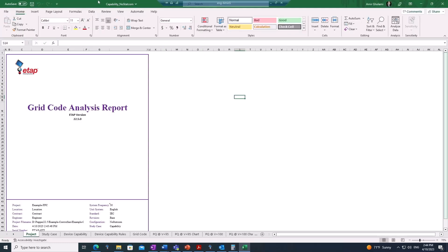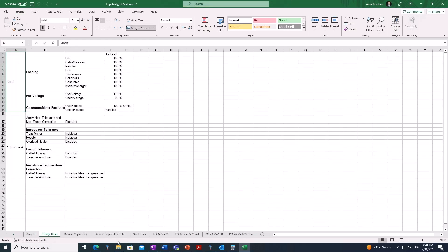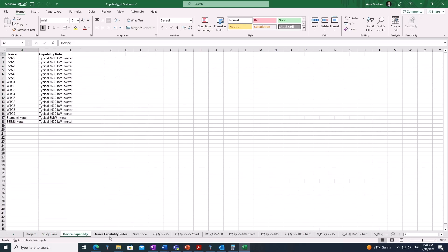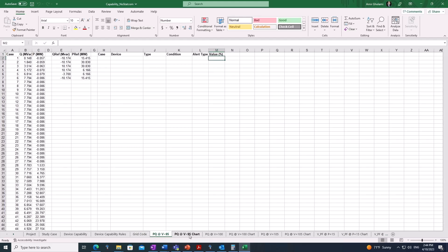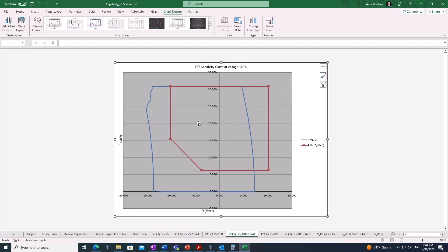Running the 'capability no STATCOM' scenario generates a report as soon as the studies are completed. The report includes various sheets covering multiple pieces of information regarding device capabilities, the grid code being used, and calculation results at different voltage levels — at 95% and 100%. The results are also visualized, making it very easy for the user to validate if their plant is capable of generating as much reactive power as the grid mandates, or if it has deficiencies.